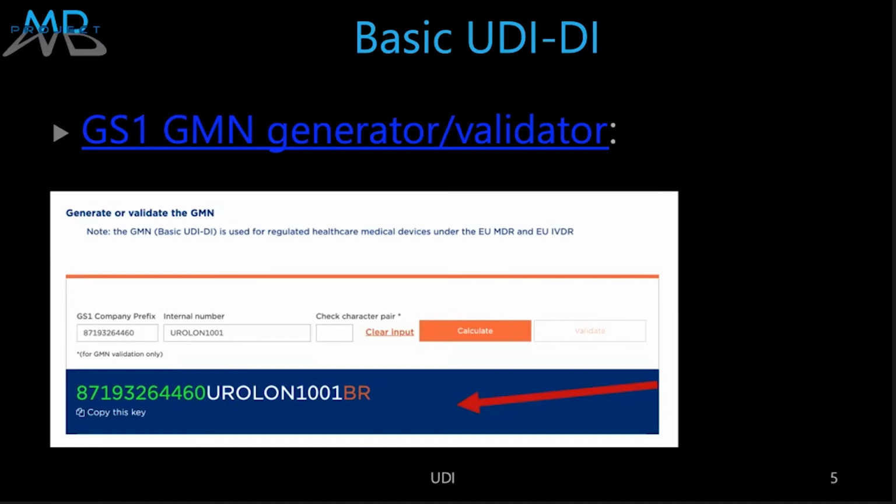So does that answer your question, Shalou? Yes, I guess it's more clear, because what I used to do is tell people this is just one basic UDI for a product family, and you can have 10 UDI-DIs under it. And they were really very confused, because I was really not clear. I guess now it makes it more clear, because I myself know, okay, this is your product family, then you can have 10 versions of the same instrument, but you don't need 10 basic UDI-DIs for that. You just have one. Absolutely correct.